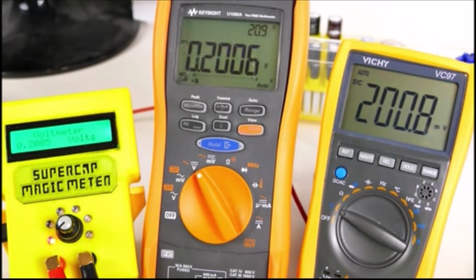So 0.2 volts is what we are trying to achieve to get 100 milliamps across the shunt. So that's an important voltage. If we go to, say, 0.1, it's off by a fraction of a millivolt there. And likewise, if we go up to higher voltage, here's 1 volt. It's off by almost 0.1 millivolts.